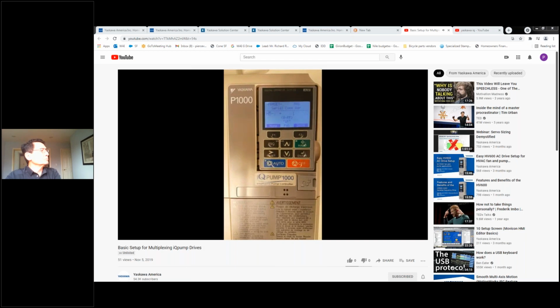With the 05 blinking, press Escape twice to get the H flashing. Change the H to a P using the up arrow and press Enter. Press Enter 3 more times to change the value of P101. Change this value to a 3 for Memobus Network and press Enter.